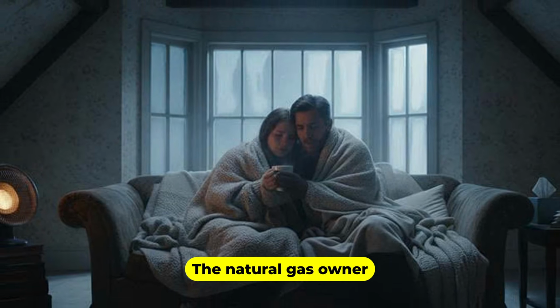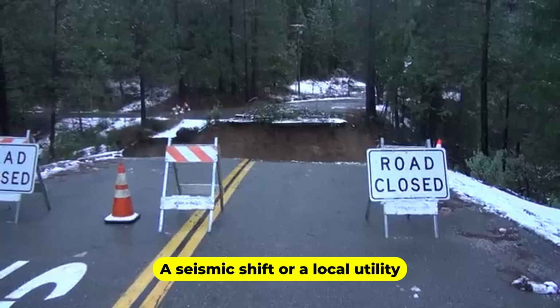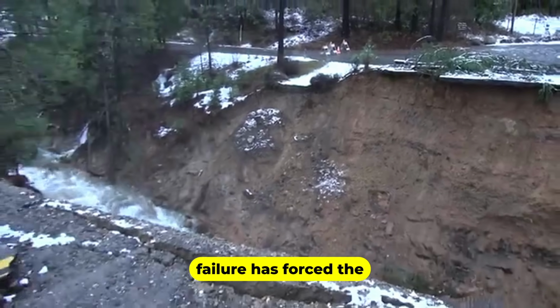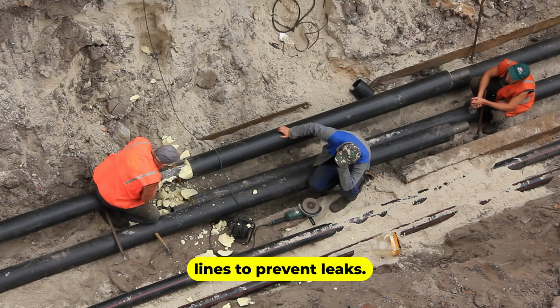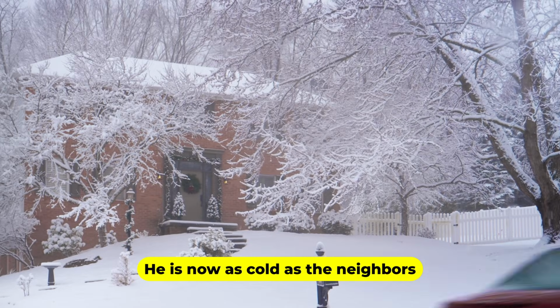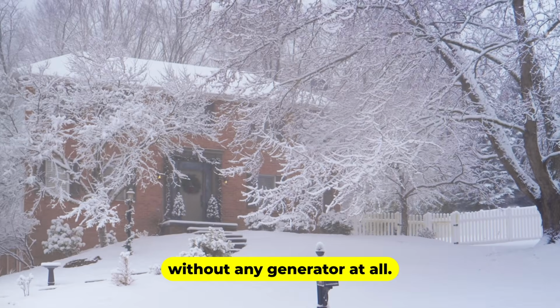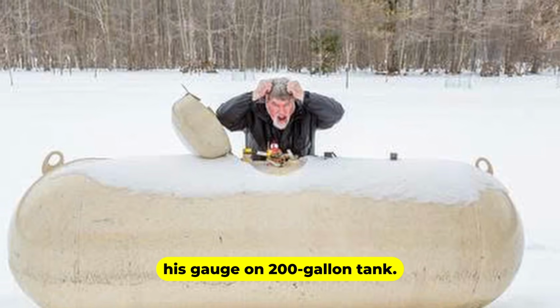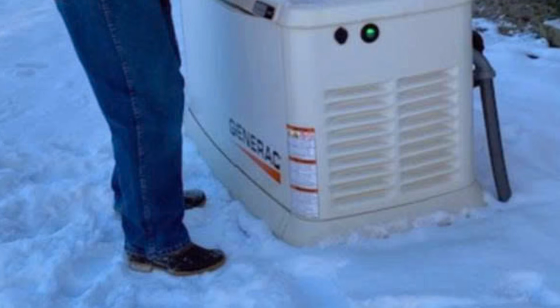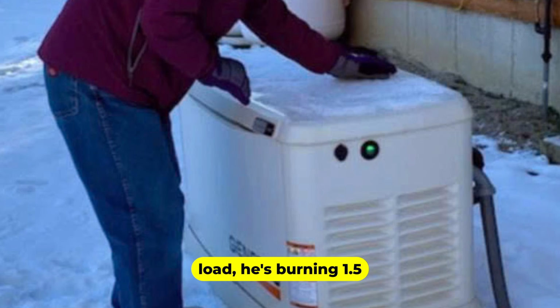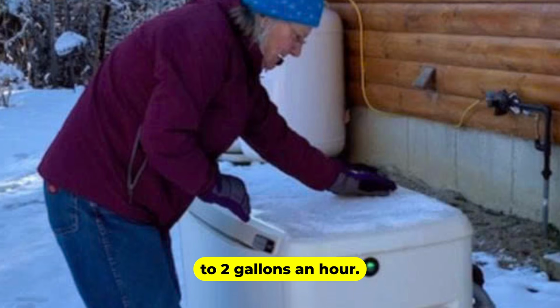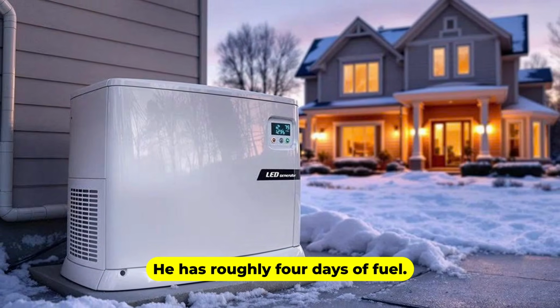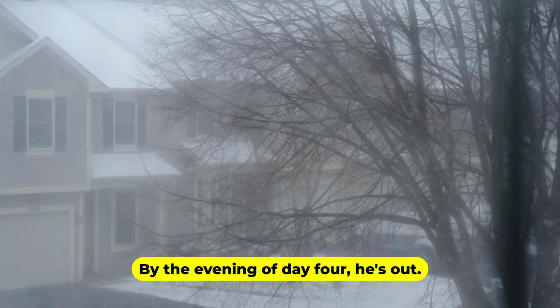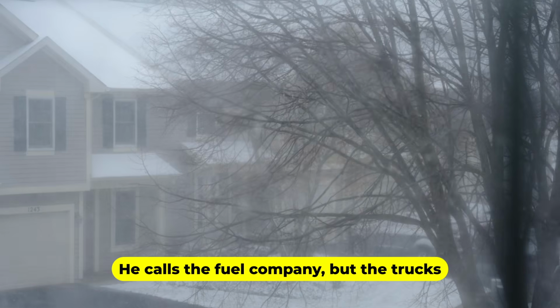The natural gas owner wakes up to a cold house. A seismic shift or a local utility failure has forced the gas company to shut down the lines to prevent leaks. He is now as cold as the neighbors without any generator at all. The propane owner is checking his gauge on his 200-gallon tank, running his 20 kilowatt unit at half load. He's burning 1.5 to 2 gallons an hour. He has roughly 4 days of fuel. By the evening of day 4, he's out. He calls the fuel company, but the trucks can't get up his icy driveway. He's in the dark.